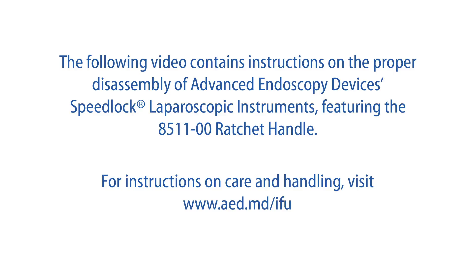The following video contains instructions on the proper disassembly of Advanced Endoscopy Devices Speedlock Laparoscopic Instruments featuring the 851100 ratchet handle. For instructions on care and handling, visit www.aed.md/ifu.